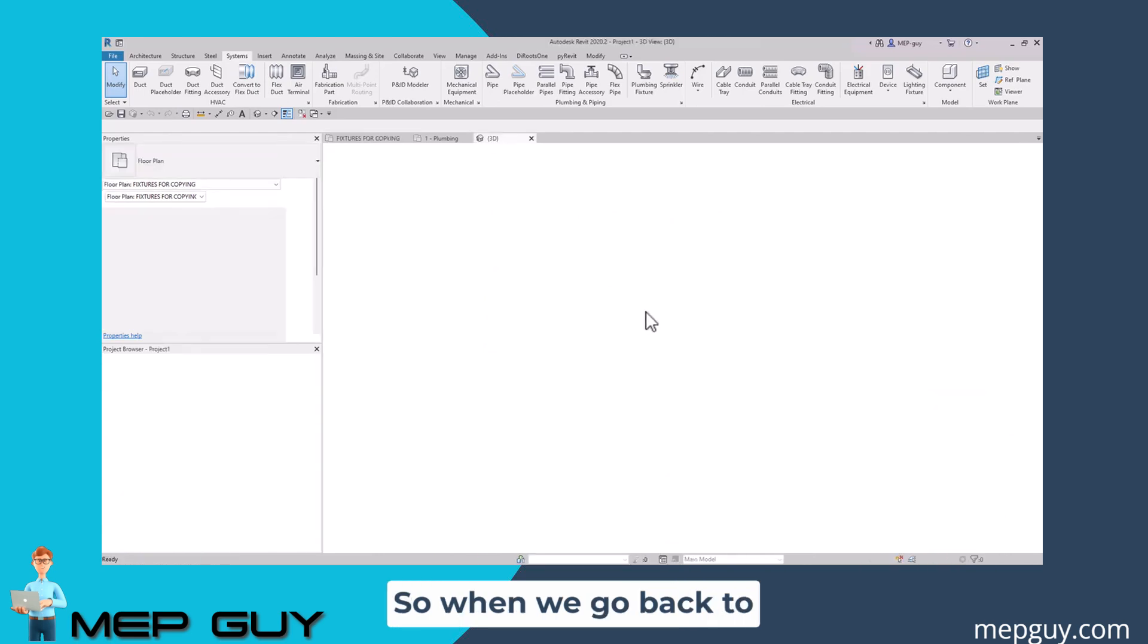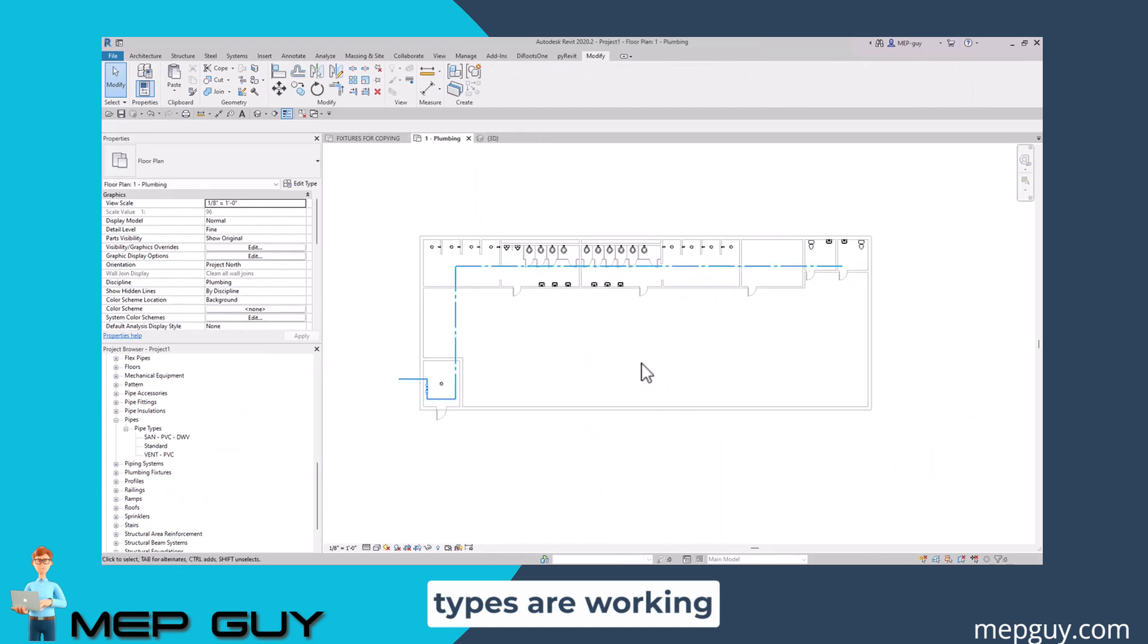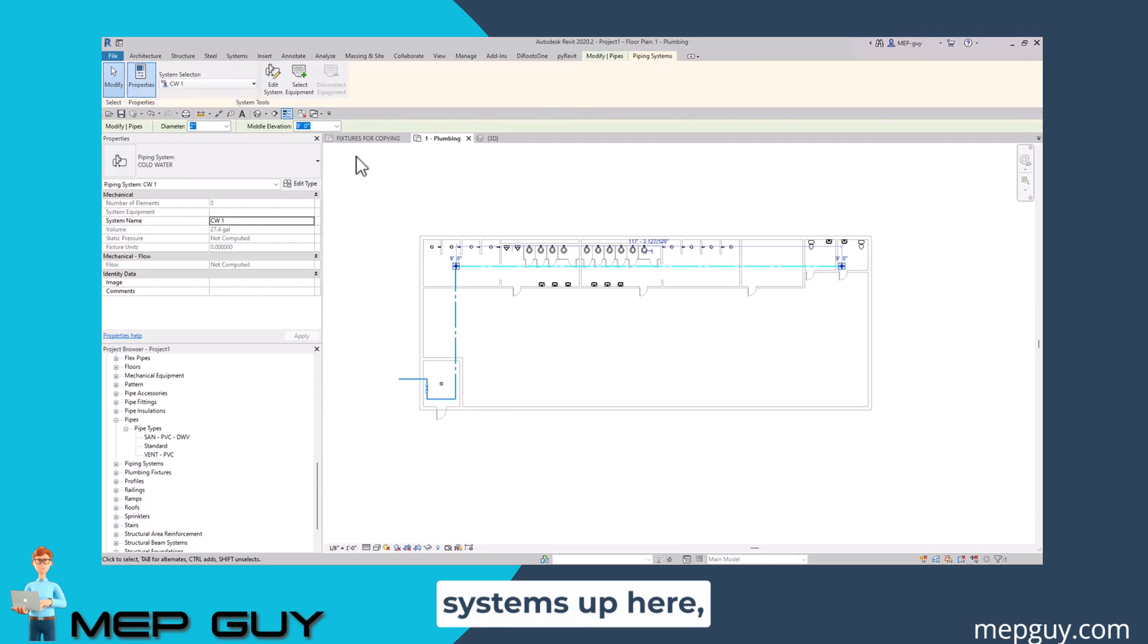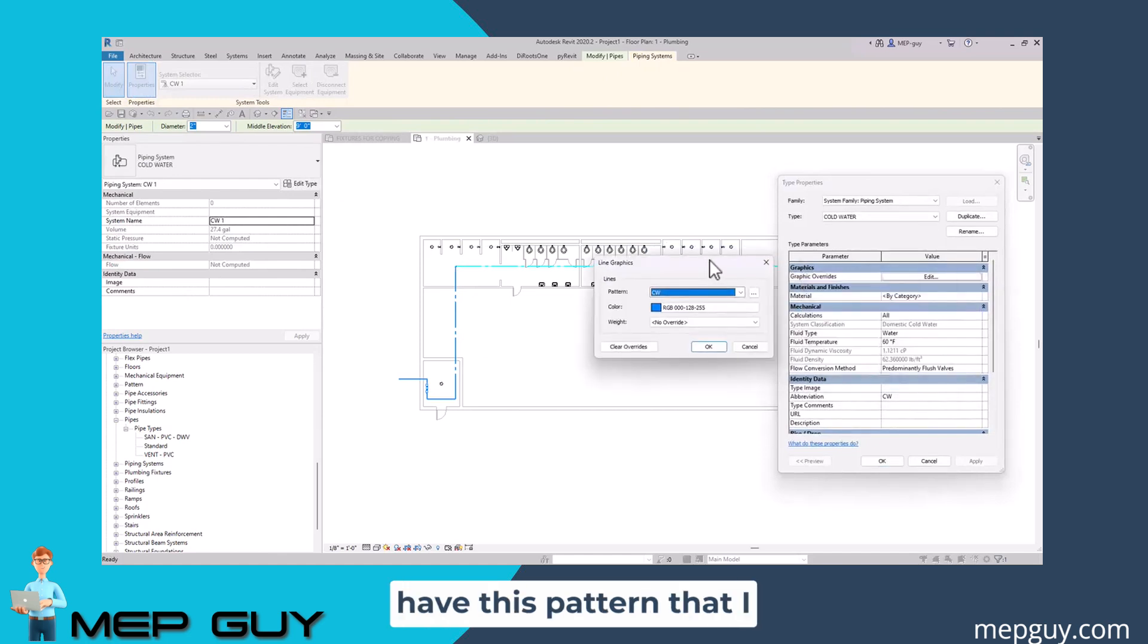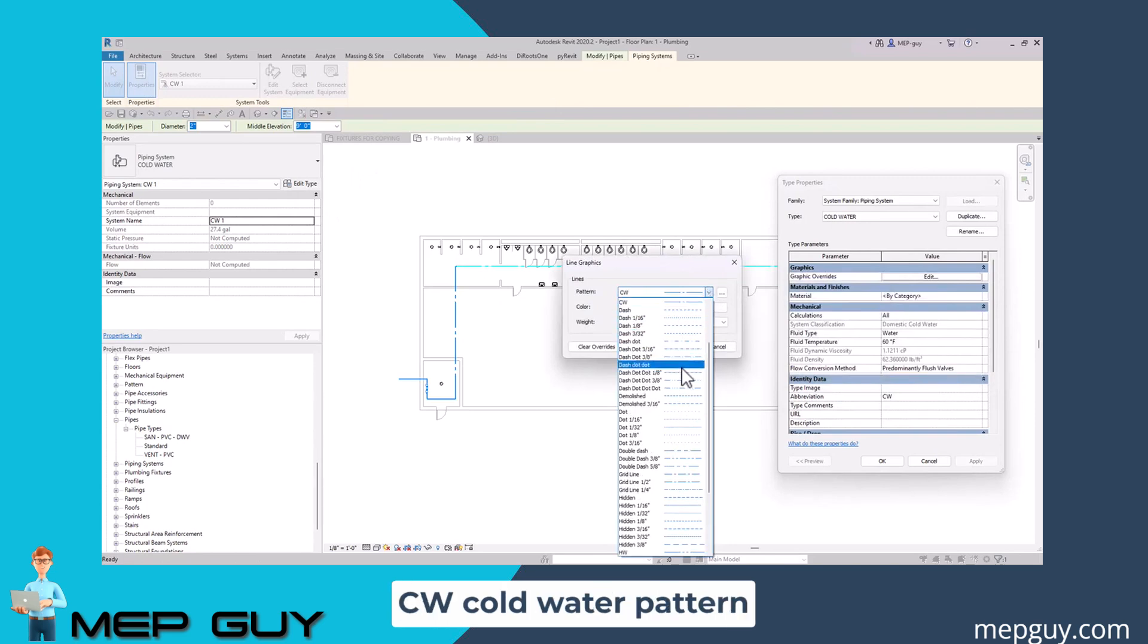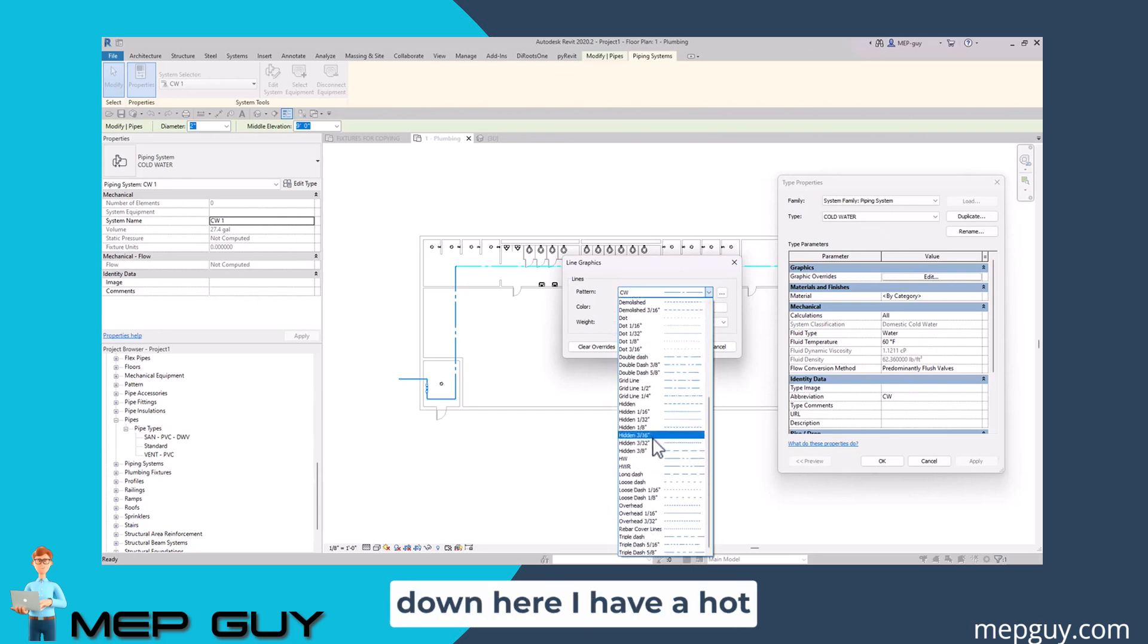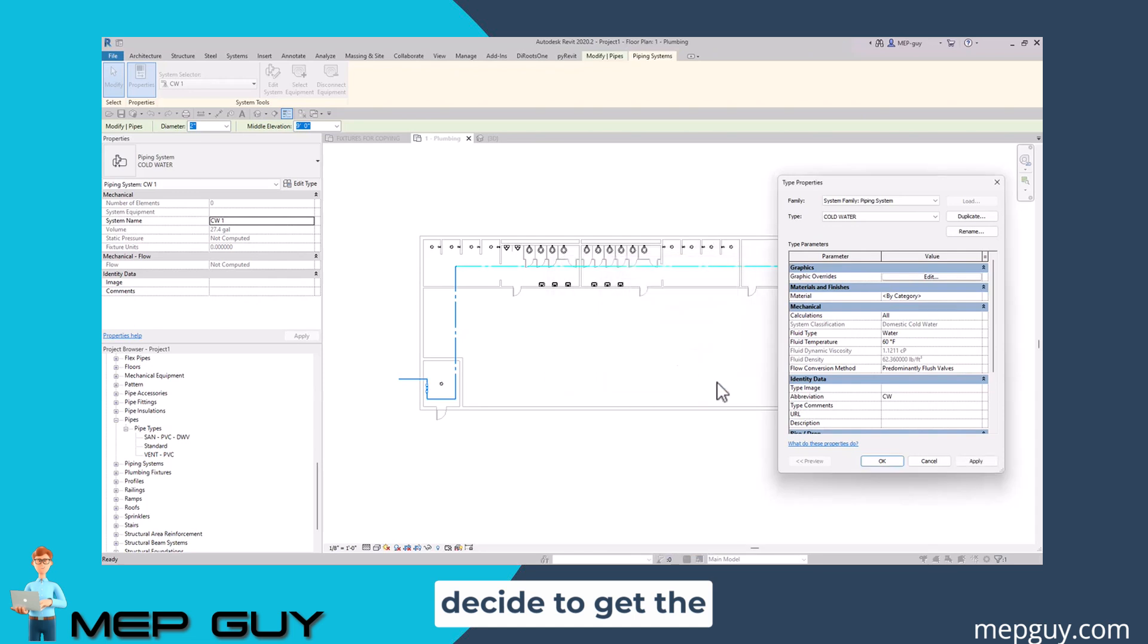When we go back to our floor plan, you can see the line types are working perfectly. If we want to change those, we would go to piping systems up here, edit type, and under graphic overrides, you can see I already have this pattern that I imported in called CW. You can also see that down here, I have a hot water and a hot water return pattern as well. So all that stuff is already set up if you decide to get the template.